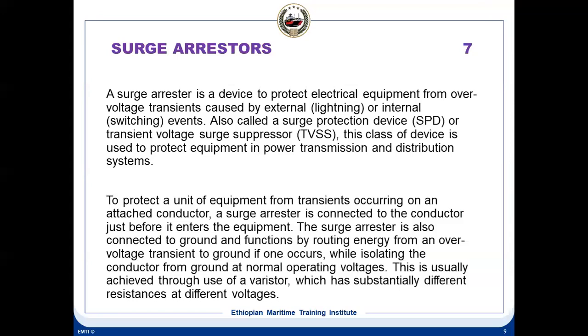To reduce the transients, we use surge suppressors. Even in an extension board, you'll find surge suppressors. The whole purpose of a surge suppressor is to reduce the transient voltage. Transient voltage means intermittent voltage which comes in between, like spikes, voltage spikes. That is the purpose of these surge arresters. How does a varistor work? As the voltage varies, the resistance varies. So a varistor changes its resistance with different voltages.